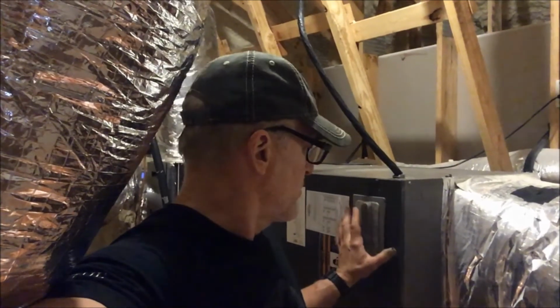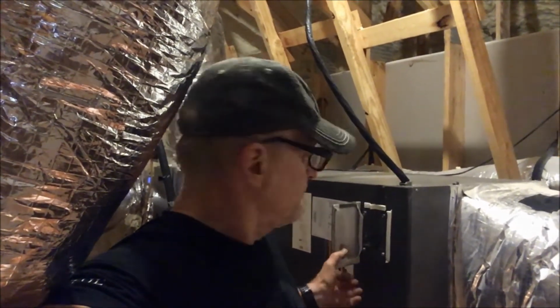Now I'm up in the attic at the air handling unit, and what you see behind me is another breaker that controls all the function within the air handling unit. I pulled open this panel, and I flipped the breaker off and then back on, and I got continuity. There was power on the thermostat. Everything was working properly, but I noticed a lot of corrosion coming out of the switch. So I flipped it back off, went downstairs, turned the main breakers off, got some CRC electrical contact cleaner, sprayed it in this breaker, turned everything back on, and it wasn't working once again. So I decided I needed to pull the whole panel off, check that breaker, and it turns out that there was massive corrosion all the way around that breaker.